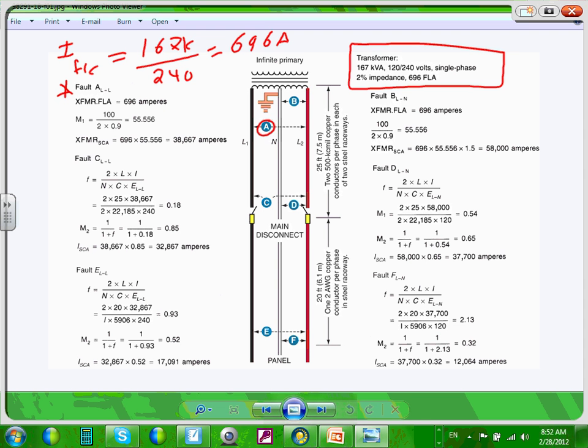That's the first thing you do. You start with the transformer. Find the full load current of the transformer. Any question about this, guys? If that was a three-phase, what would you add next to the 240? 1.73. Okay? Step number one, guys, we're going to find the full load current. Here's step number one. Done. Any question about finding a full load current of a transformer? Single phase, you use the single phase formula. Three phase, you use the three phase formula.